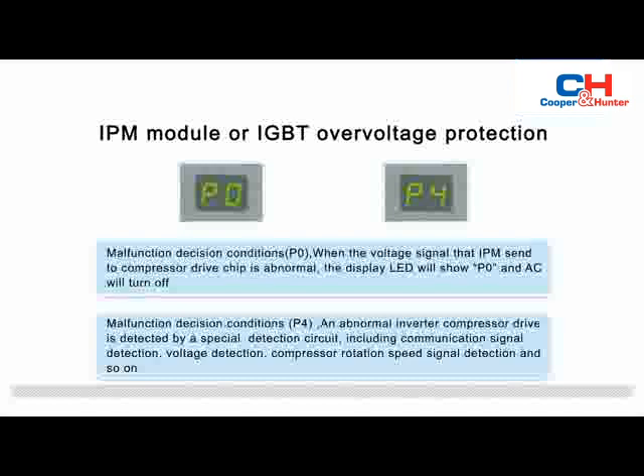Malfunction Decision Conditions — P0: When the voltage signal that the IPM sends to the compressor drive chip is abnormal, the display LED will show P0 and the air conditioner will turn off.